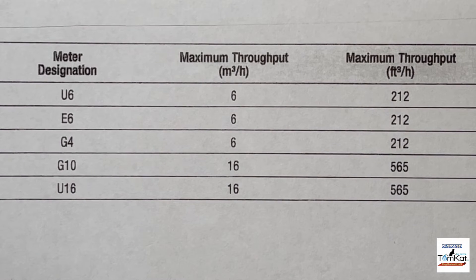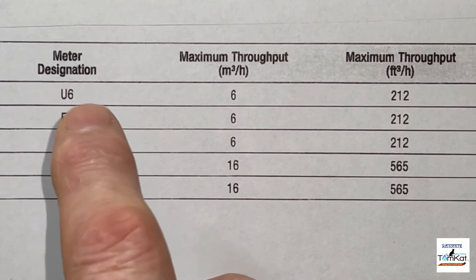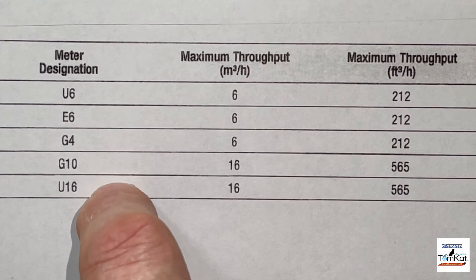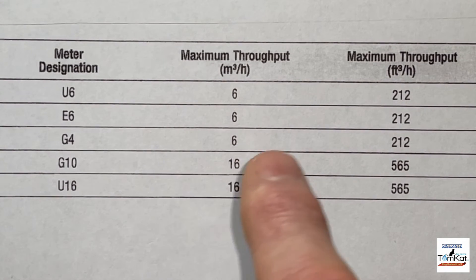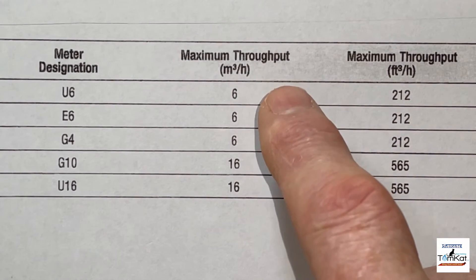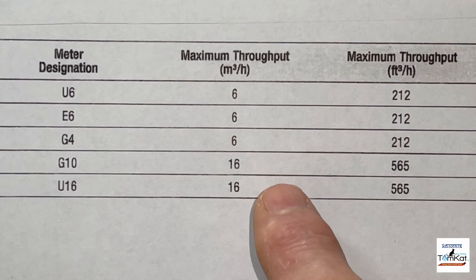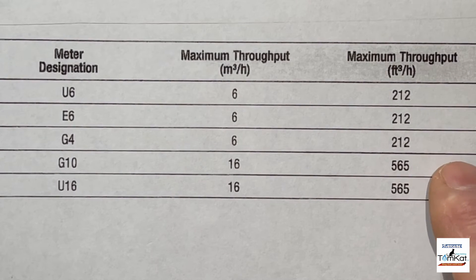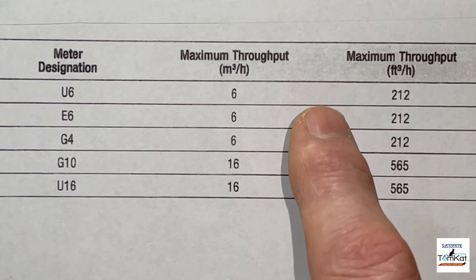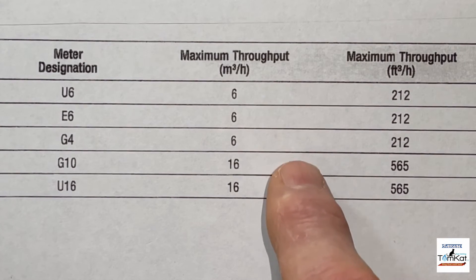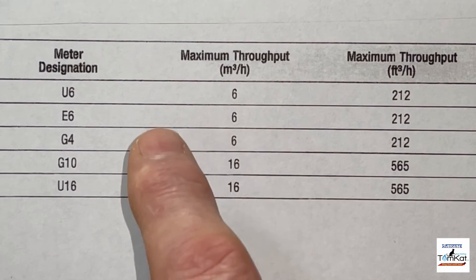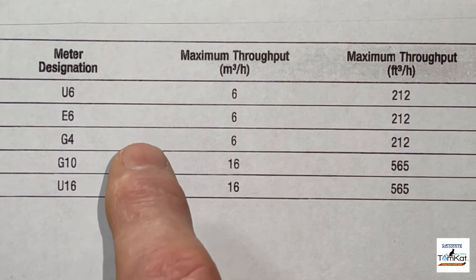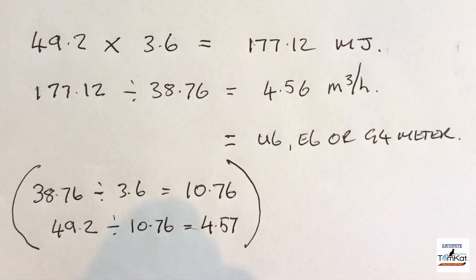Now look at the meter selection chart. As a domestic engineer you can work on U6, E6, G4, G10, and U16 meters. The U6/E6/G4 gives us six meters cubed per hour, the G10 gives 16, and so on. Our result of 4.56 m³/hr is less than six, so we can use a U6, E6, or G4 meter.